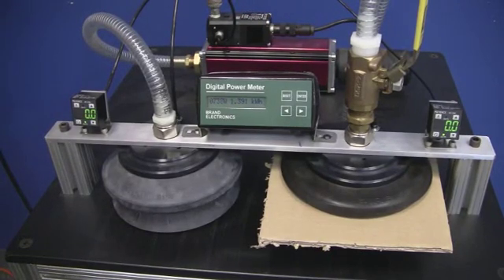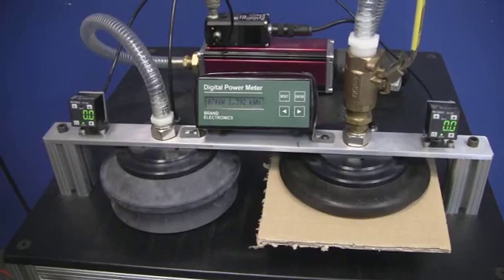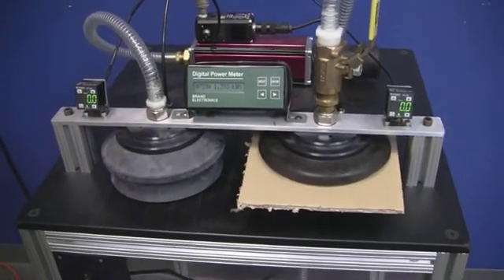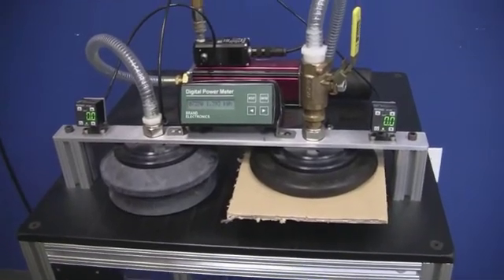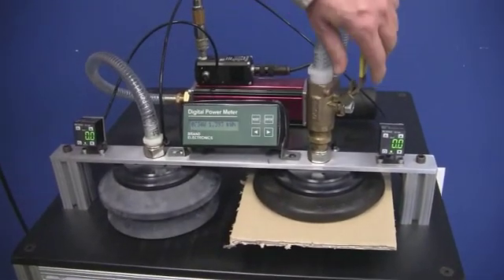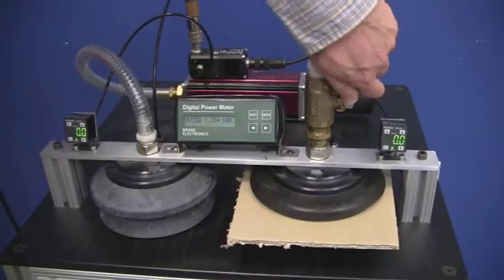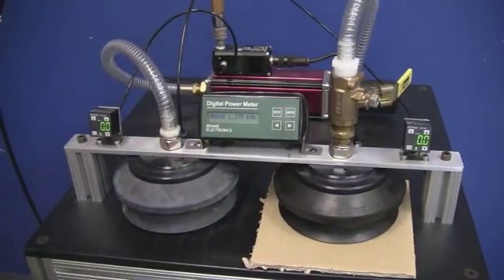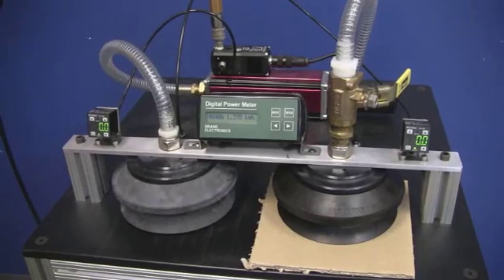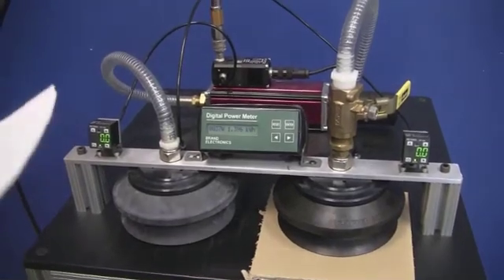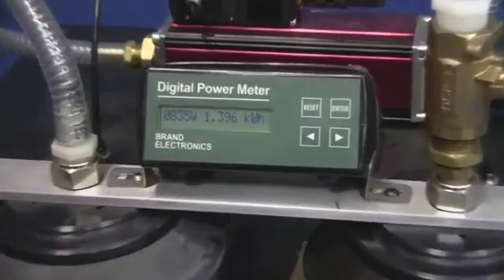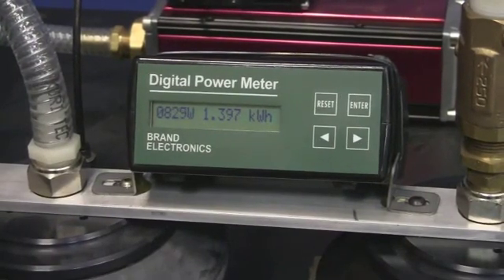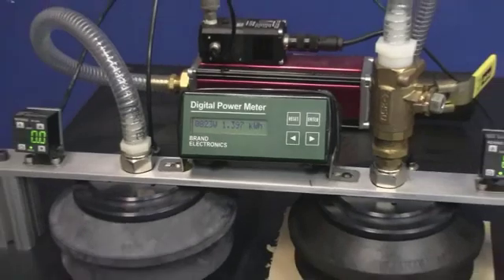Now when we want to release what's on the cups, we have to block the vacuum flow to the cup as well as open a passage to atmosphere so that the vacuum will be broken inside the cup. And we're going to do that with this vacuum valve. Now when we do this, the energy jumps up to over 830 watts, well over one horsepower. It's a little bit ironic that in this state, the pump is using its most energy when it's doing no work at all.